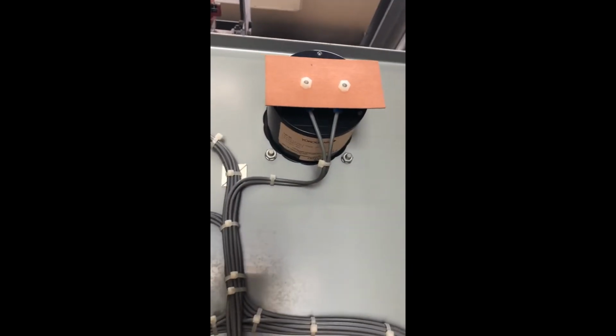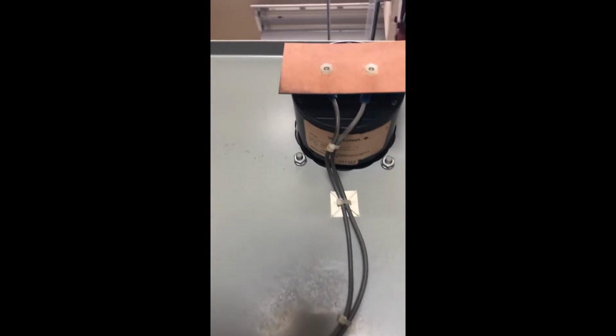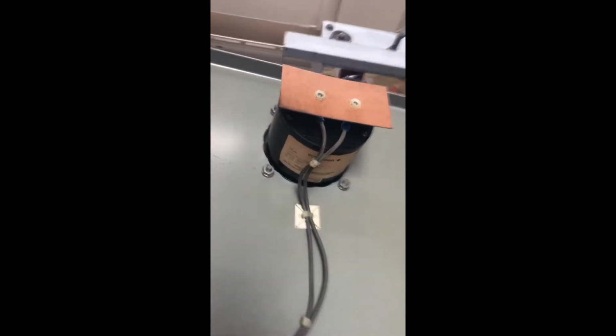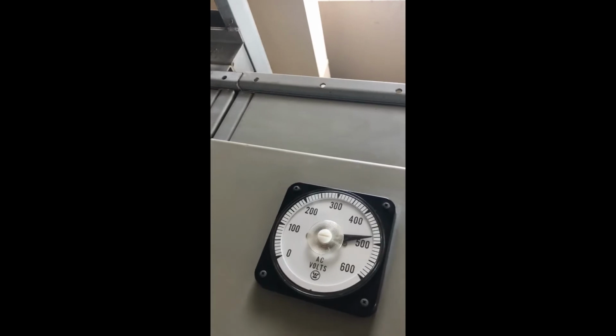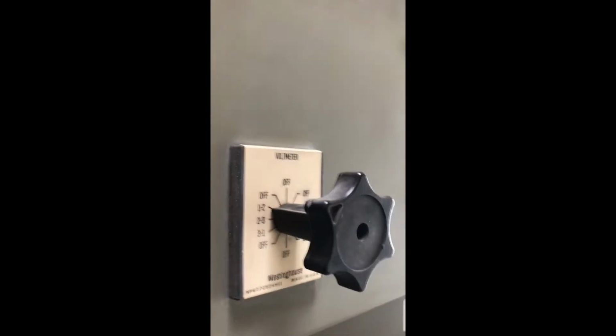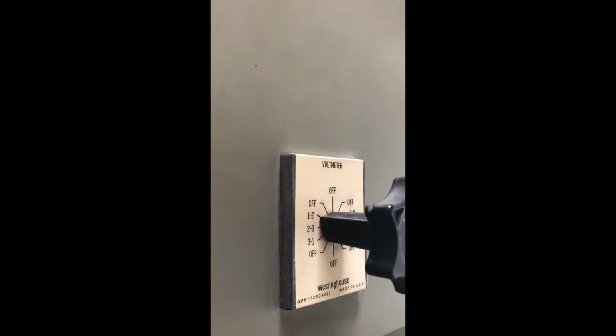So it's safe to open this door. And you just got a couple little wires there, but it's actually measuring the voltage to this entire facility. And here is the current, measuring the current of the entire facility. So right now, we look good. We've got, like we said, about 480 volts. I have a selector right here. So right now, I'm looking at 1, 2, A B.